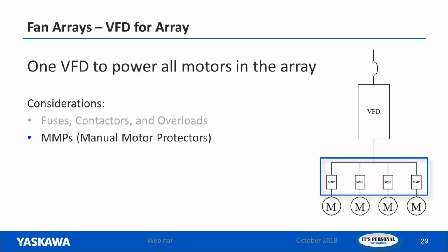Now, in some cases, you can replace that with MMPs, the manual motor protectors I mentioned earlier, and that can take care of the overload protection. These are, like I said, manual motor circuit protectors, and they're able to open up the circuit now. You don't have to have contactors.